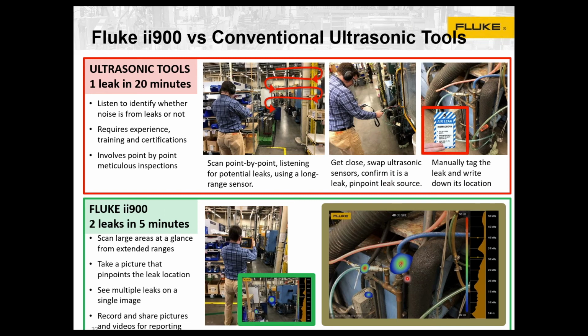Using the acoustic imager, you can very easily sort between what's a leak and what's a reflection. So if you see something like this, all you need to do is move to the left, move to the right. A leak source will stay in the same spot and be constant. A reflection will move as you move or perhaps disappear. So again, armed with some user tips, almost anybody could use acoustic imaging effectively, quickly to find leaks.